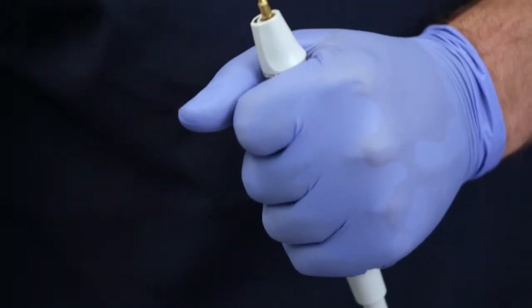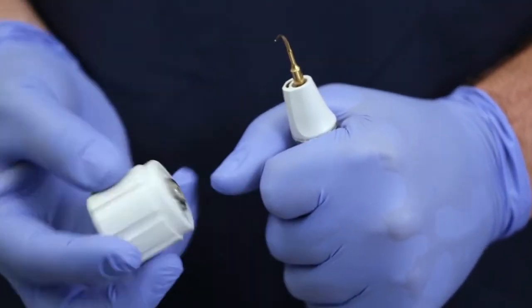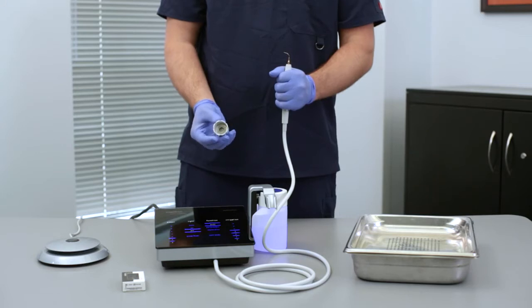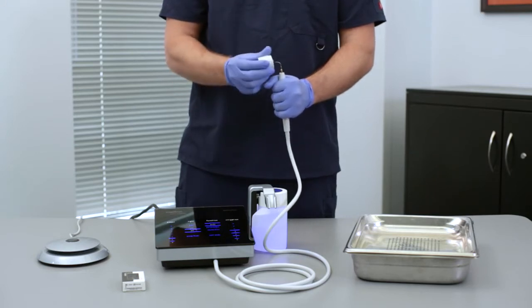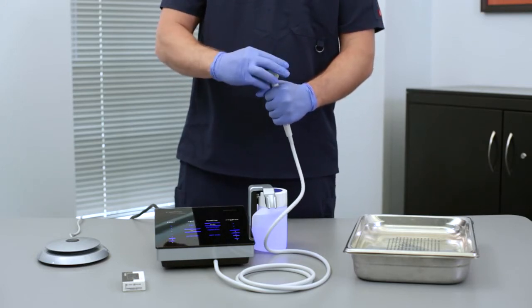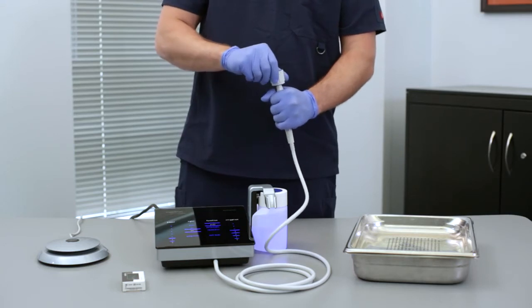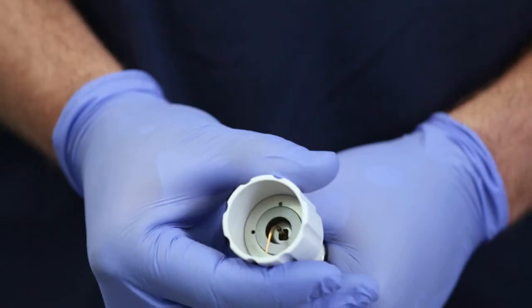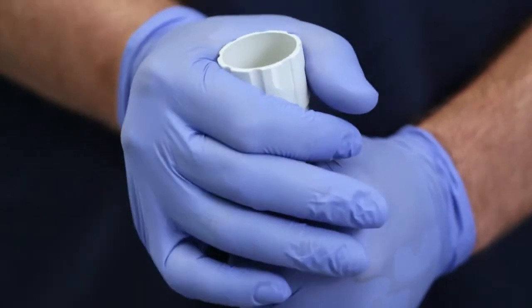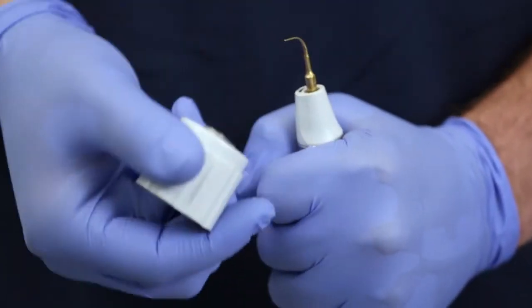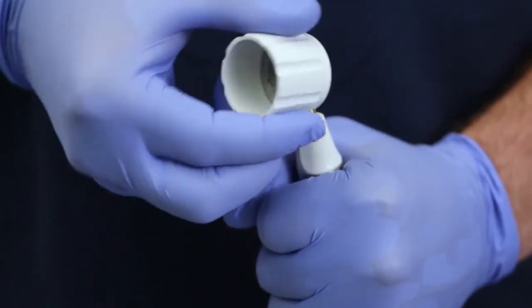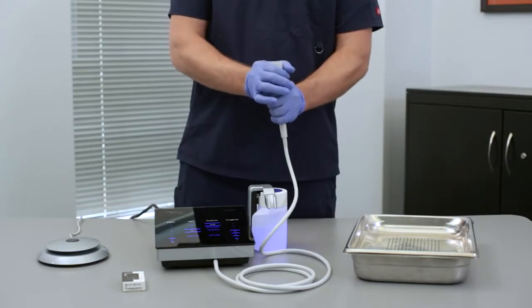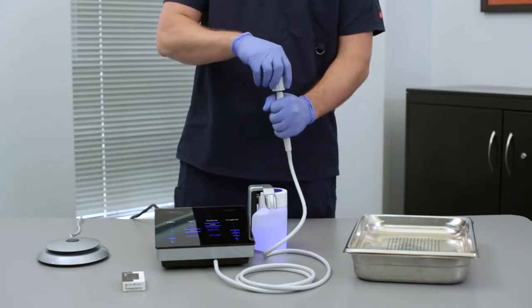Locate the K6 torque wrench, which looks like a small gray cup, and place it over the insert tip with the open end pointed toward the ceiling like a cup. Grasp the wrench from the side, not over the top, and then turn it clockwise until you hear a loud click. To loosen and remove the insert tip, use the torque wrench in the same manner, but turn it counterclockwise. There will not be a loud click to loosen the tip.